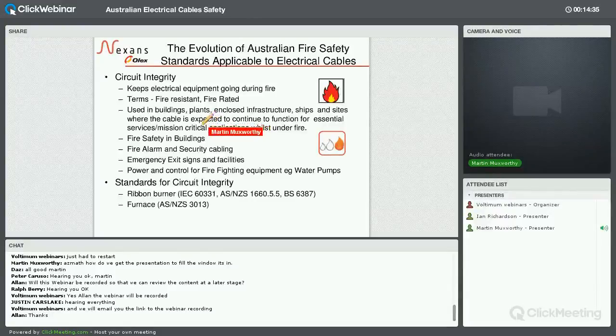Where are circuit integrity cables used, or fire rated cables used? Buildings, plants, enclosed infrastructure, and I've mentioned a few other areas there. Anywhere where the function of the circuit is essential and critical to continue operating during a fire, and I guess lighting for exit paths, things like that. Fire alarm and security cable, fire safety in buildings, in the case of say lift mains and things like that, are where they're commonly used. Water pumps, it should be fairly obvious that water pumps need to be able to operate in the case of a fire.